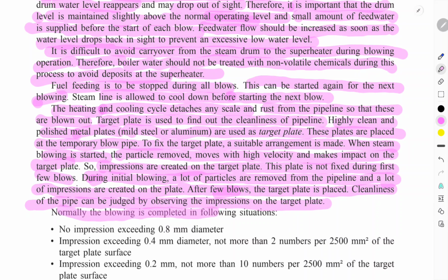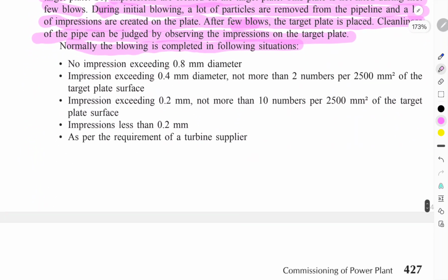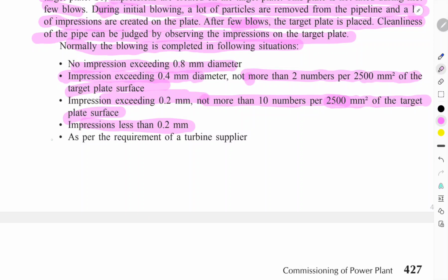Normally, blowing is completed under the following situation. No impression exceeding 0.8 mm. Impressions exceeding 0.5 mm diameter should be no more than two numbers per 2500 mm square of the target plate surface. Impressions exceeding 0.2 mm, not more than 10 numbers per 2500 mm square of the target plate surface. Impressions less than 0.2 mm, if any, are as per the requirement of the turbine supplier.